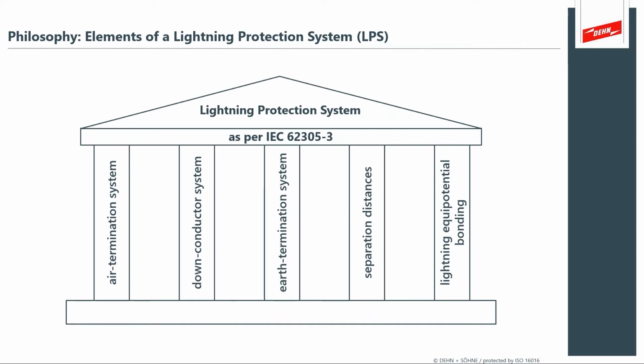So, the elements of lightning protection. Once we've decided what LPL level, now we can determine the air termination, the down conductor system, the earthing system, separation distances, and lightning equipotential bonding. By selection of the LPL class, now we can design the system for the air terminal placement, the density of and the design of the earthing system, and of course the selection of surge protection measures. And so these are all dependent on that risk analysis. So start at your risk. Now you can start to apply the lightning protection elements. And you need to pay attention to all 5 of these elements. If you ignore some of them, what you'll see is more high risk of lightning side flash into an unprotected system.